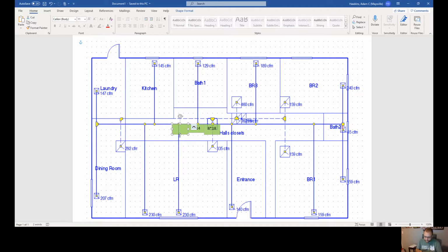Hopefully you're catching the hang of this. 0.1 at 500 looks like an 8 by 12. So after you take anything out of it, this is the way I do it. Now, there's different ways to do it. There's different ways to design it. If you look in Manual D, there's a couple of different methods that are different than this. This is the way I was taught. After you take anything out, you reduce it. All right, so your next piece is going to be big enough to carry everything that's left.